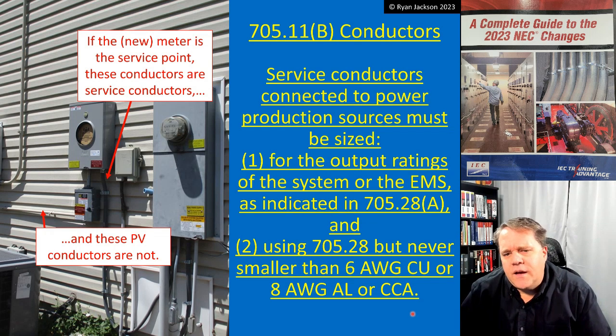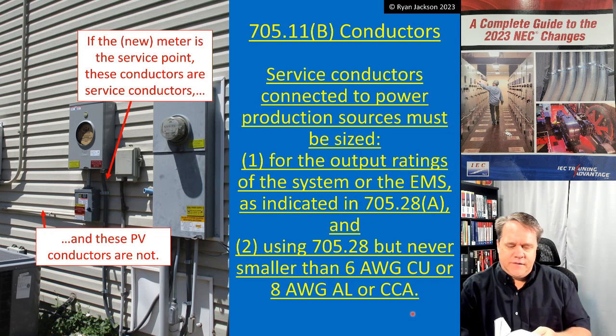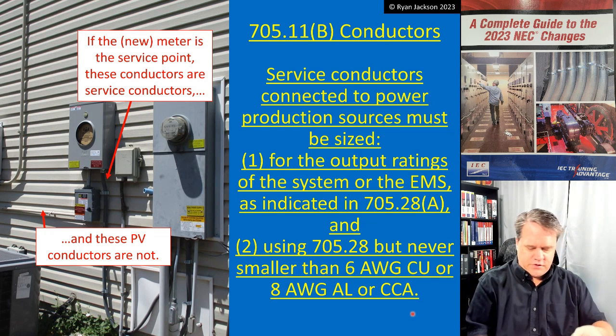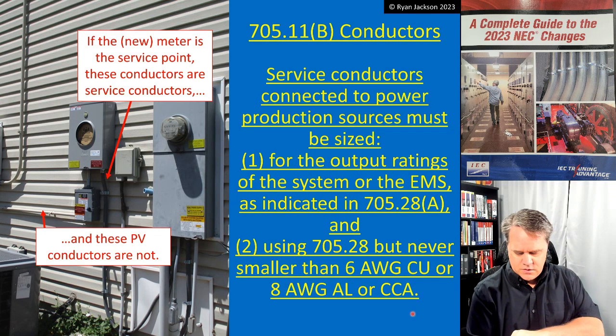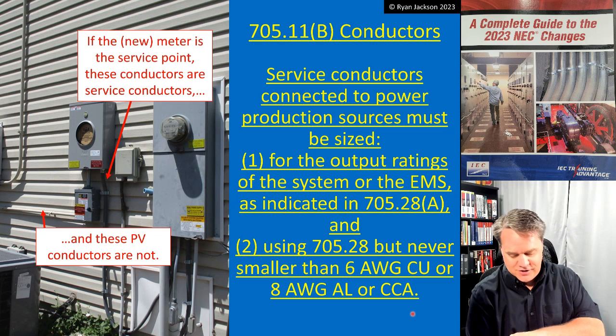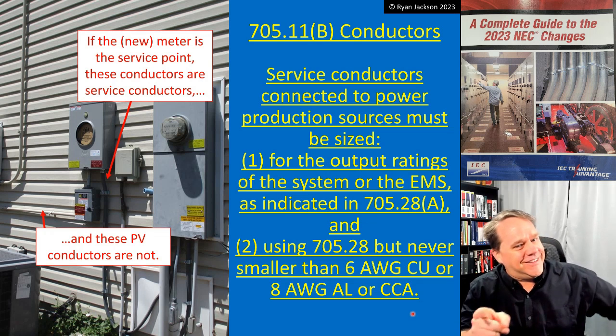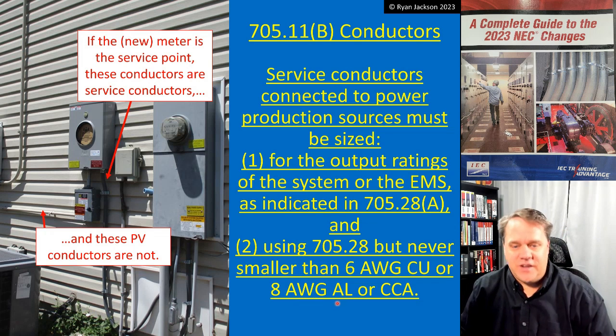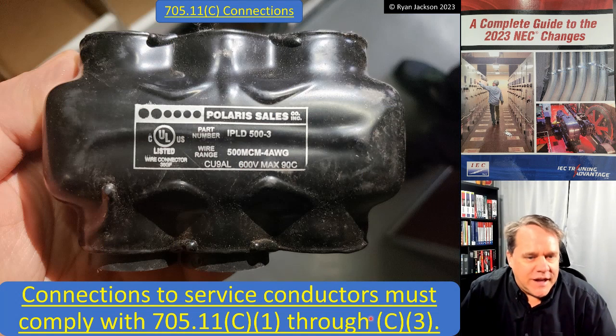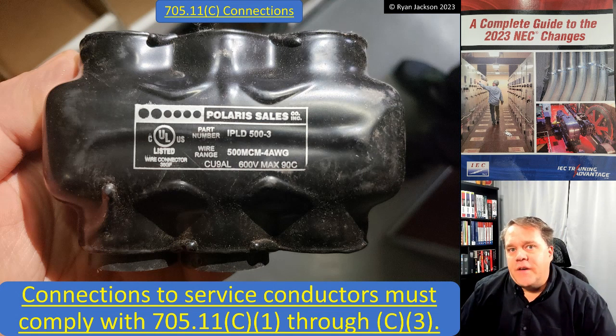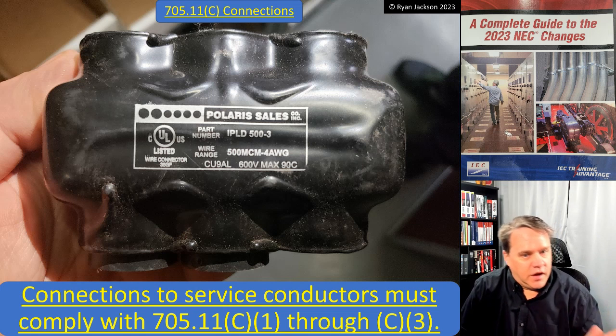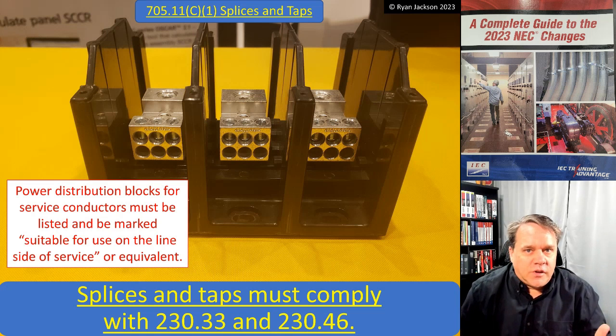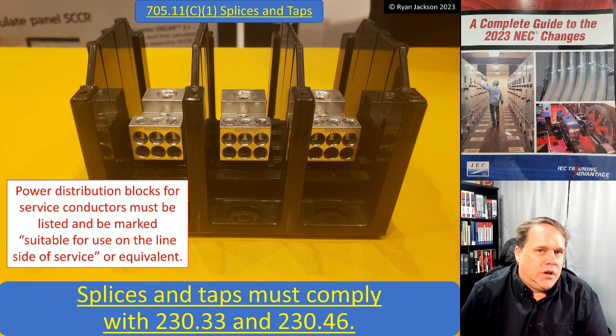Actually, that doesn't make sense. Let me check 705.11 — and we're going to keep this in the video to show I'm not a robot and I make mistakes. Yes: it's 6 AWG copper or 4 AWG aluminum or copper-clad aluminum. I had a typo there — my apologies. So 6 AWG copper or 4 AWG aluminum or copper-clad aluminum. Moving on: connections to service conductors must comply with 705.11(C)(1) through (C)(3), which defaults back to Article 230.